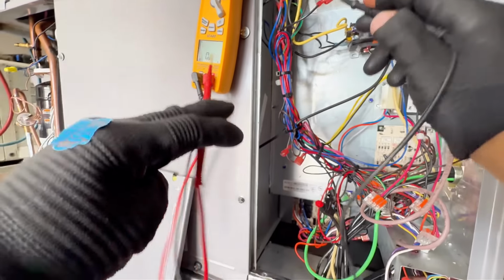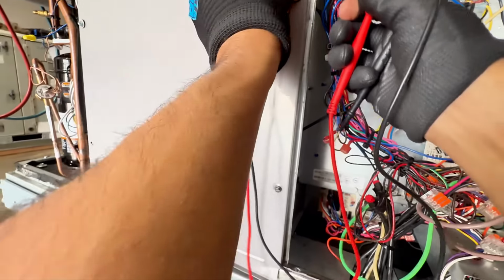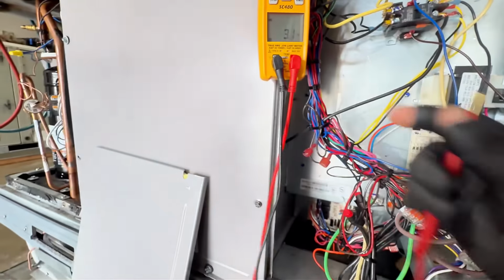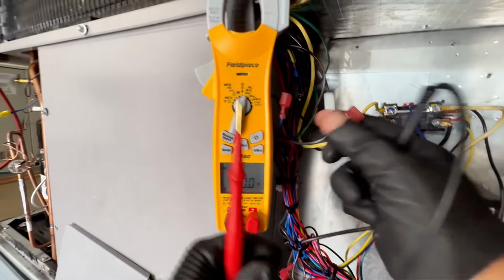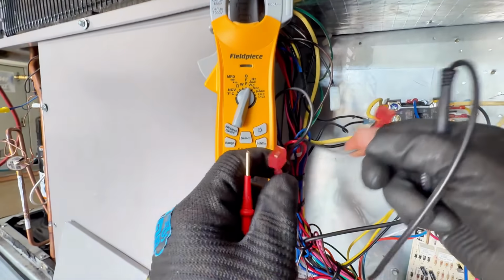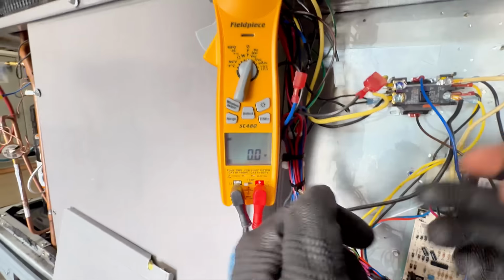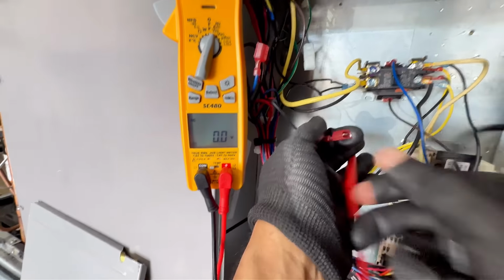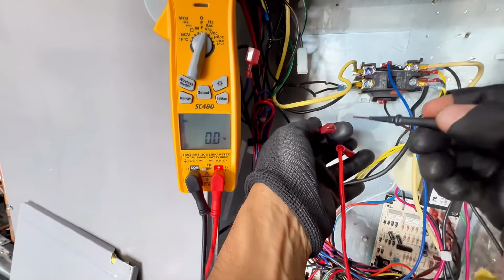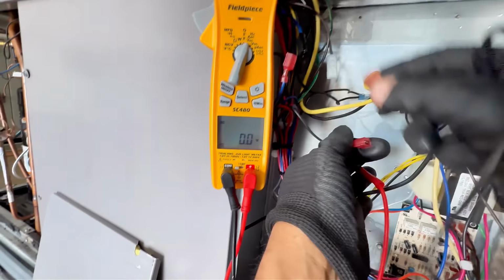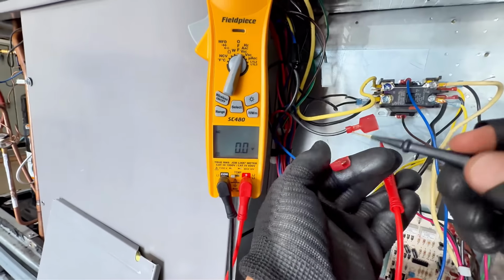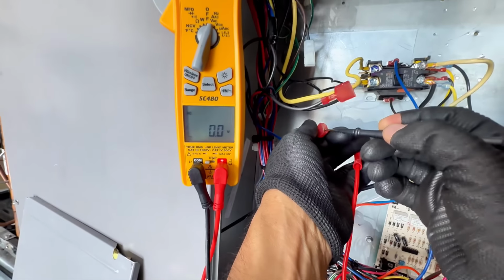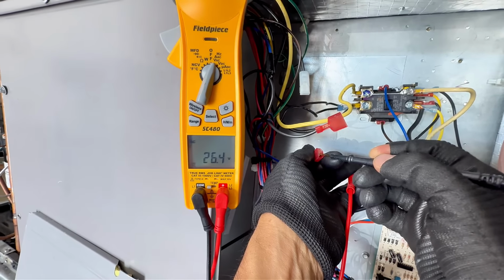But another thing you can do, remember I've said, compare common to a leg to see if you have 24 volts. So I know that I got 24 volts because you see with these right here, one of them is 24 volts and then it comes back. And I think it's going to be that blue one. So I'm going to check just the chassis and one wire here. Okay, so this is the one that's sending 24 volts from the board. You see? 24 volts. So that's good.